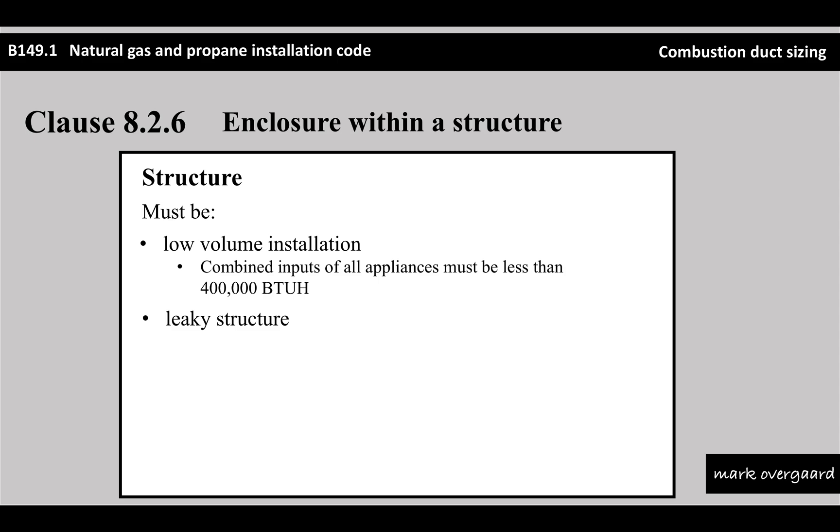The second thing is it has to be a leaky structure, which means it doesn't comply with Clause 8.2.1 A or B from the codebook. It's not airtight - air can come from outside the structure into the structure. Another part of this is that the volume of the structure is able to handle any air requirements, meaning the structure is leaky enough that enough air can get in to feed those appliances what they need to work.